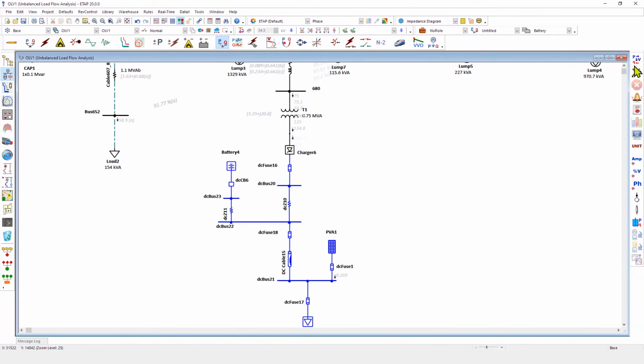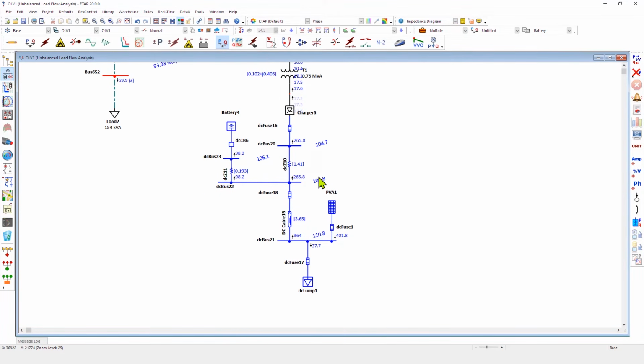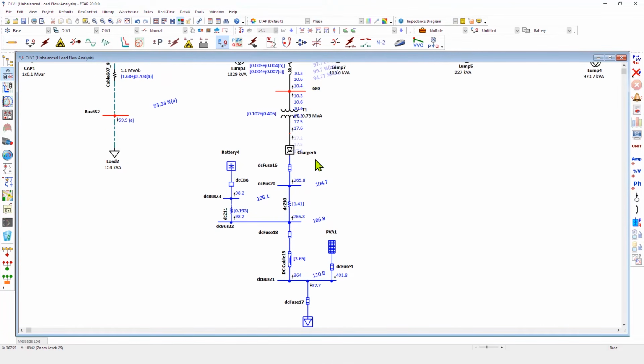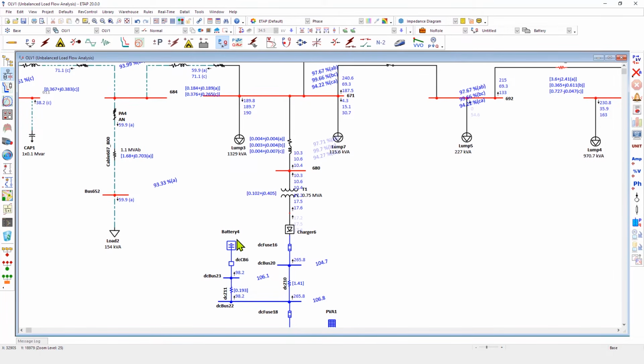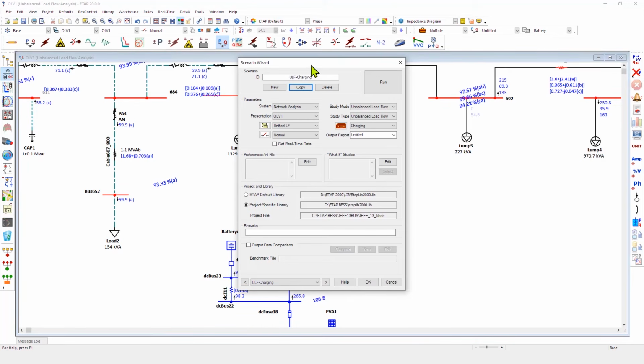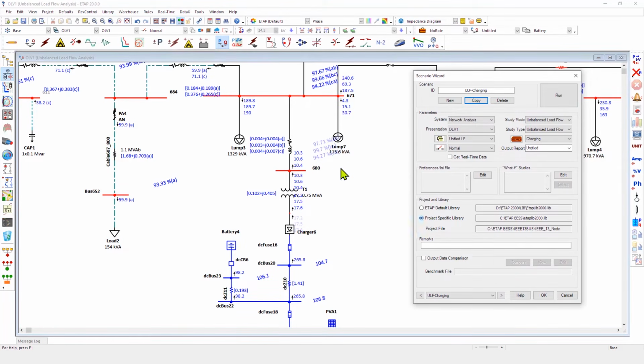So once again, when we go ahead and run our unified power flow, we can observe what happens when we have an AC and DC system that are interconnected together. We're now beginning to see what would happen when the DC network is connected to the AC side and what is now the complete picture or the power flow between these two systems. Let's go ahead and run a couple of cases using this unified load flow where we can see the interaction between the AC and DC system as we vary loading on the DC side.